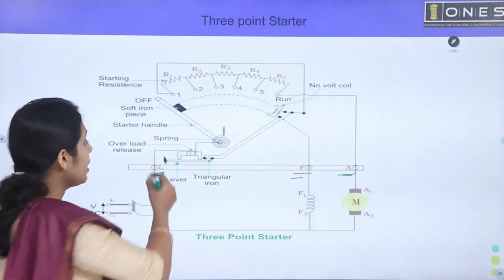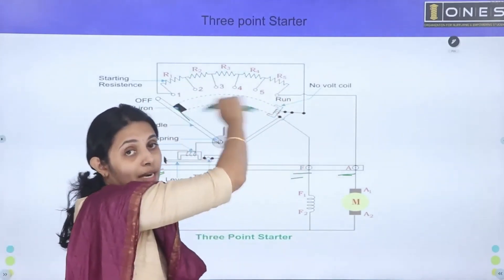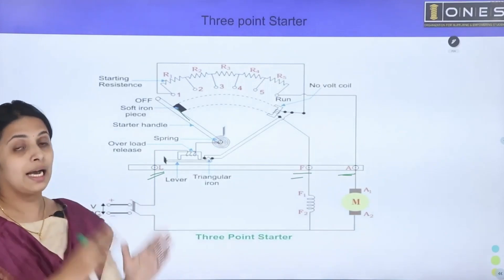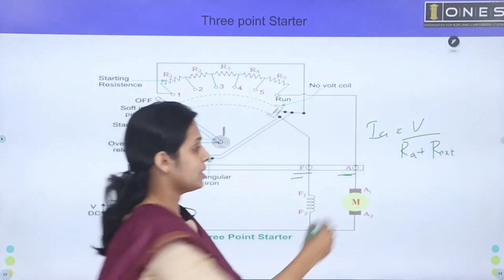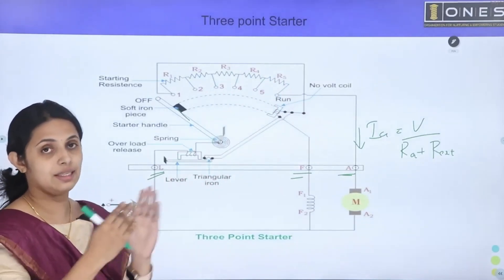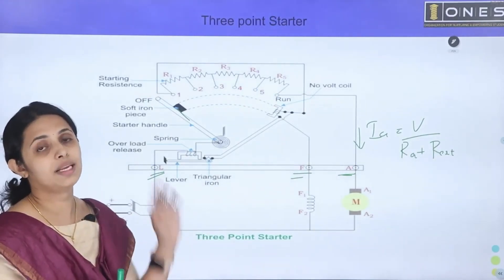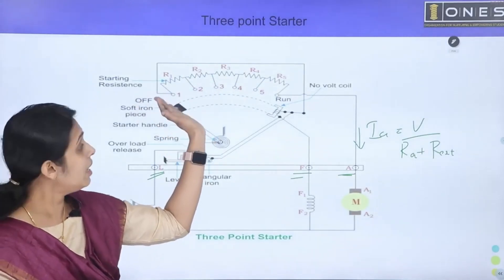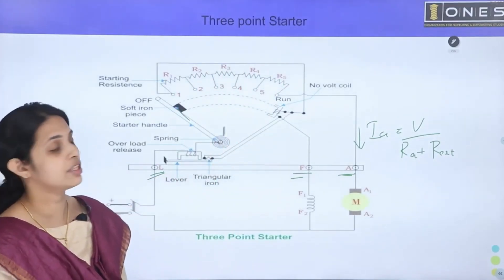When we move the starter lever, the starting resistance is gradually reduced. As the motor picks up speed, back EMF builds up and automatically reduces armature current. When the motor reaches full speed, the full resistance is cut out of the circuit.